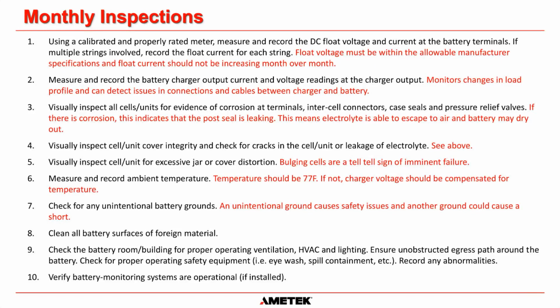You should measure and record the ambient temperature of the room, and that temperature should be 77 degrees Fahrenheit. If not, then the charger voltage should be compensated for temperature. So if the temperature goes up, then you should compensate the charger voltage down, and vice versa. If the temperature is cooler than 77 degrees Fahrenheit, then you have to increase the voltage of the charger.